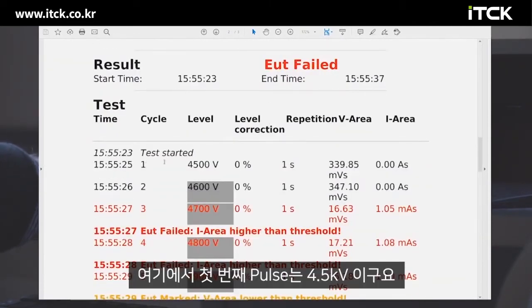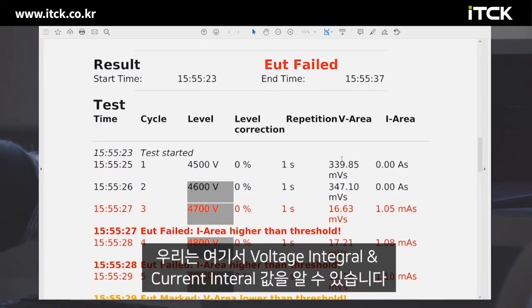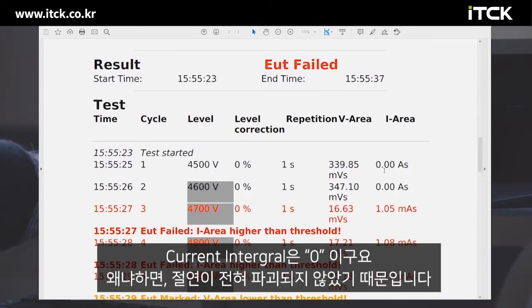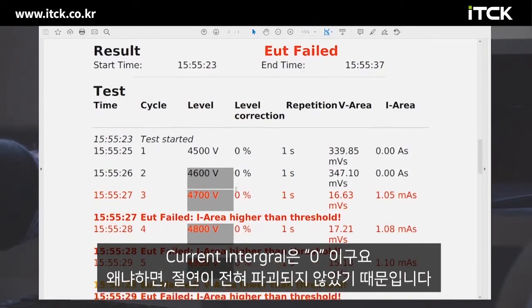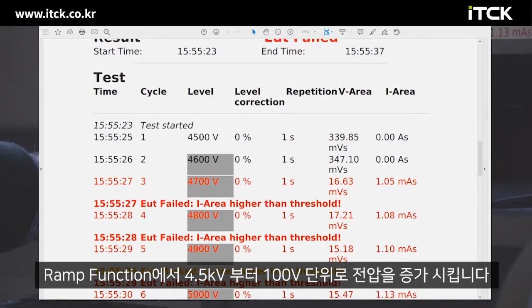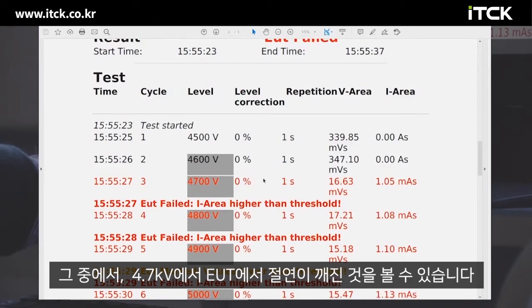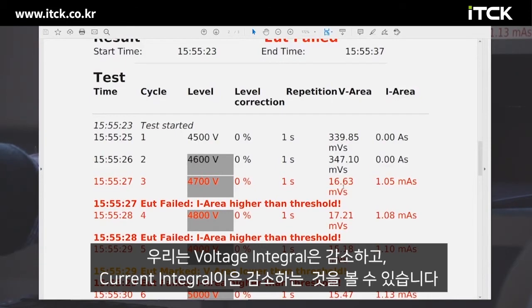Here, the first pulse is 4.5 kilovolts, and we have the voltage integral and the current integral. The current integral was 0, so there's no breakdown. Using the ramp function, we increased from 4.5 in 100 volt steps, and at 4.7 kilovolts the test object broke down. We see the voltage integral has decreased and the current integral has increased.